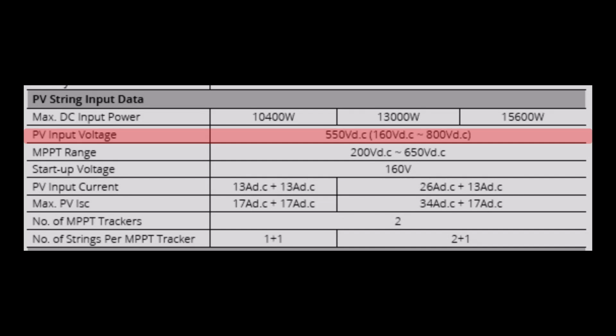The photovoltaic input voltage is between 160 volts DC and 800 volts DC. DC stands for direct current. But you can see that the MPPT management range goes from 200 volts to 650. So you wouldn't really like to get it up to 800 because the MPPT couldn't manage that kind of voltage properly. So when you're designing your string, make sure that the voltage in the string adds up to less than 650 volts DC. The startup voltage is the voltage from the panels that it takes to start up the inverter, and it's probably better to have this at least 220 volts to get it going, and that would be 5 40 volt panels or more. So there is a minimum number of panels you can have on a string.